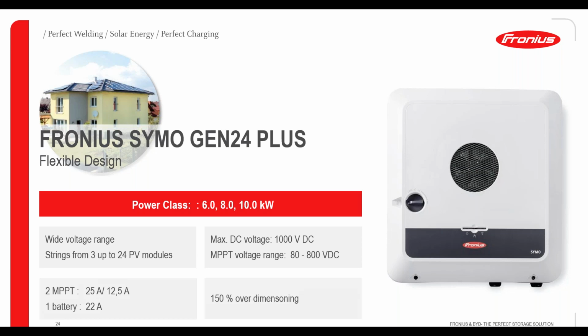If you want to oversize the Gen 24 Plus model, you can oversize it by 50%. So in case we have 15 kilowatts of solar panels on the roof, we can actually use a Gen 24 Plus 10 kilowatts and there will be no problem. So even if you have maybe an east-west roof, you can put more panels on the Gen 24.